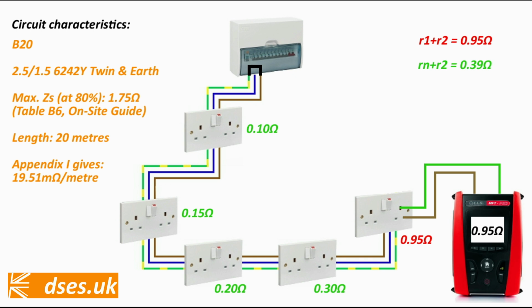But let's say we've identified that we have a problem here, and we worked our way back, checking all other accessible connections, and yet we found them to be sound. That potentially means either there's another point in this circuit we haven't located, such as a junction hidden somewhere inaccessible, probably under the floor or something lurking behind fitted furniture, or there's damage to the cable as buried in the fabric of the building between the last point which read good and the next one which is bad.